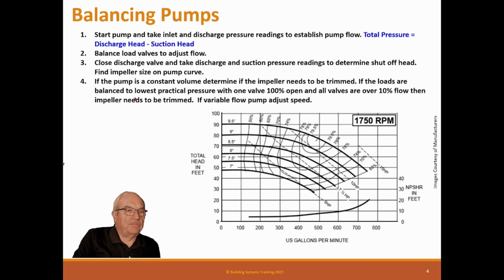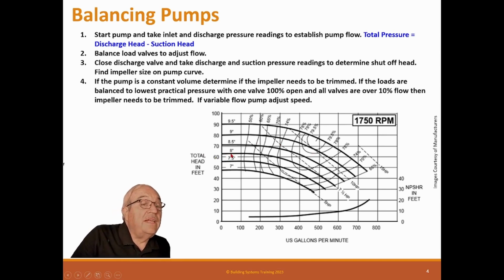All right, so here's our pump curve. So remember that here is the head, and this is the flow, and you've made a pressure reading. So you've got a differential pressure. This is the total pressure of the system. It's in feet, it's in head. So if you had about 63 feet of head, then you would have an 8-inch impeller, because your flow is 0. So here's the 0, and you read your head, and that's where your impeller is. So that's where it needs to be.